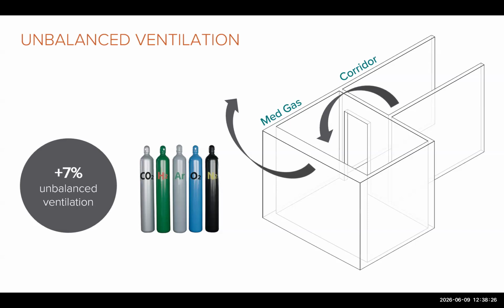And whereas normally in a passive house project, when you have an exhaust fan that's just being directly exhausted, like in a laundry room, you could bring in cold makeup air at that same rate, 1,000 CFM, and also bypass the ERV. So your ERV stays balanced. But in this case, we couldn't bring in that volume of cold air. It was just too much, and it would have made the space really cold and uncomfortable. So instead, we are bringing 1,000 CFM of makeup air through the ERV in order to preheat it.